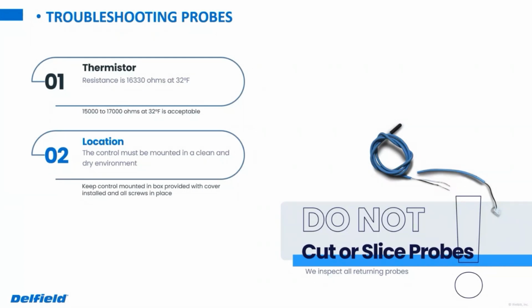Through the years, we've unfortunately seen people use wire nuts, duct tape, simply splicing wires together and calling it good. None of that is any good. None of that is right. As a technician, we always want to do the best job we possibly can. So a proper size butt connector and say 6 inches of heat shrink will save you. You won't have callbacks. Everything will work long enough that the customer will forget you were ever there, which is the ideal situation if you're a technician. So again, last resort. Don't just cut and splice them. Always look for another avenue. In the end, if you can't possibly do it a different way, then cut and splice and follow that procedure.